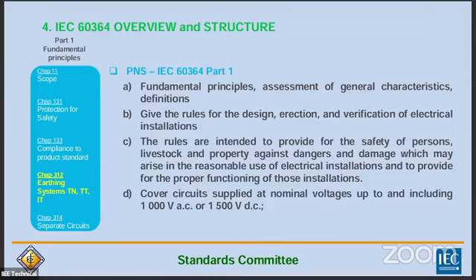What is the importance of this? This is the reference when it comes to IEC earthing systems. They don't have what's called grounded and ungrounded system - you won't find that terminology in the IEC standards. Instead they have TN, TT, and IT - that's what's used. This only covers 1,000 volts AC or 1,500 volts DC. So as you can see, fundamental principles assessment of general characteristics give the rules for the design, erection, and verification of electrical installations.